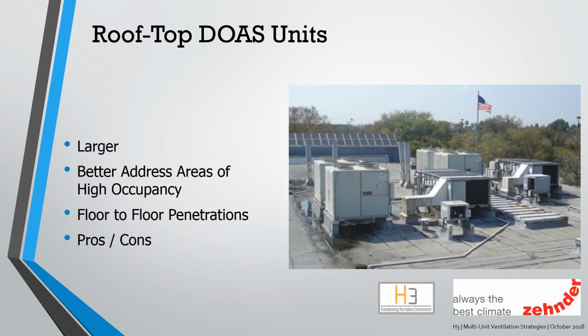We have also received a number of questions relating to rooftop dedicated outdoor air systems. These systems are generally larger units that can provide higher volumes of outdoor air to high occupancy spaces. A DOAS is well suited to replacing existing systems when ducting is already in place to provide a less invasive solution. These systems typically originate at the roof level or an outside slab and are exposed to the elements. To ventilate multi-story occupancies, they require vertical chaseways and ducting, resulting in the need to push volumes of air through longer expanses to reach the final delivery point.